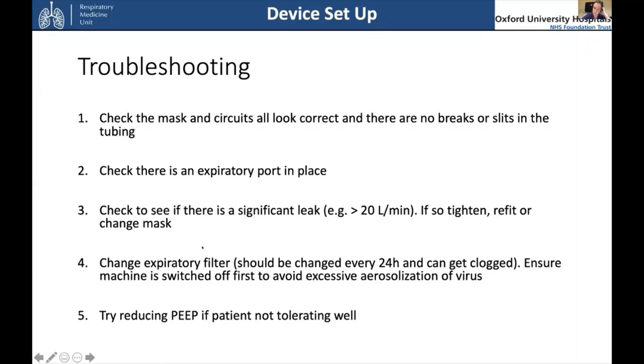If it's still not quite right, then you can change the expiratory filter, because they can get clogged - this should be the viral filter, these are the things that can get clogged. So make sure that's changed. But just make sure that you turn off the machine, turn off the device before you break the circuit. Otherwise you'll just risk aerosolizing coronavirus into the room.